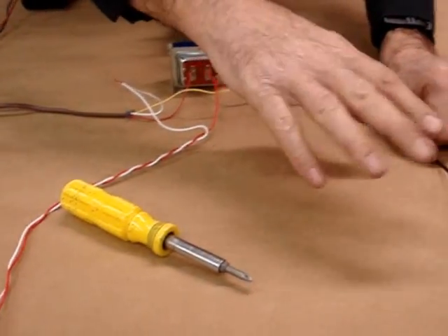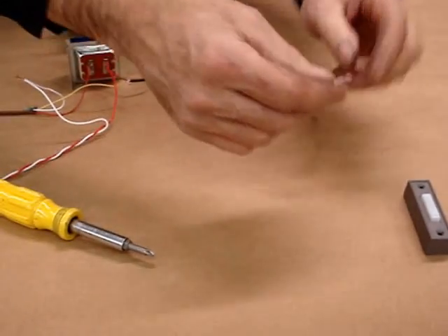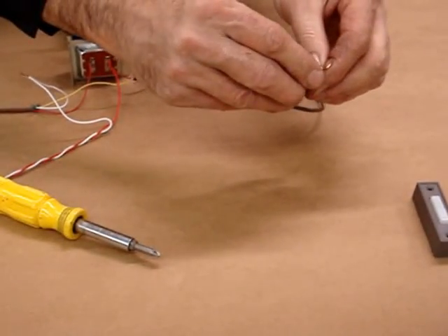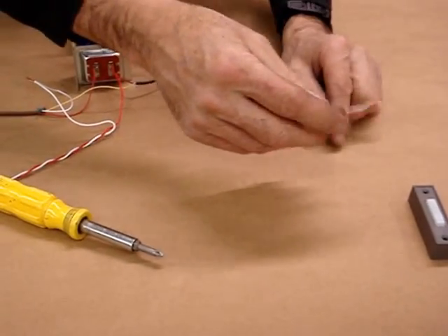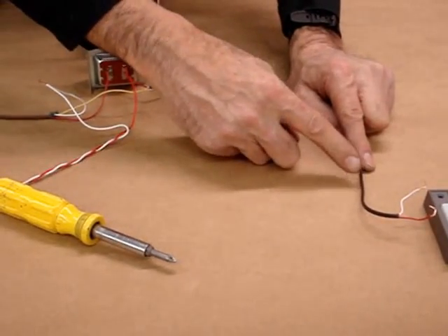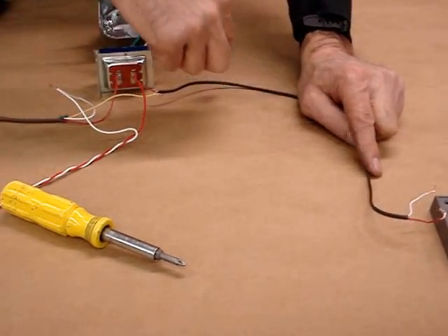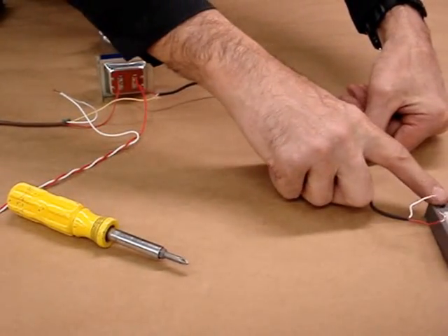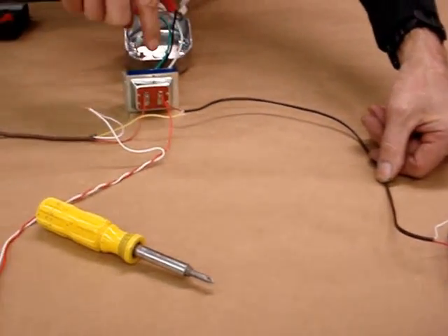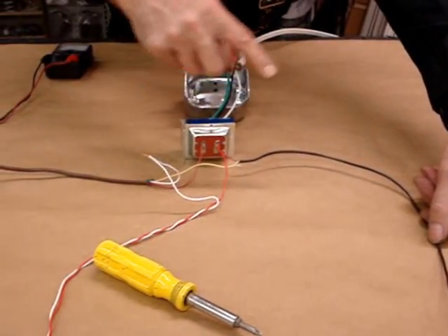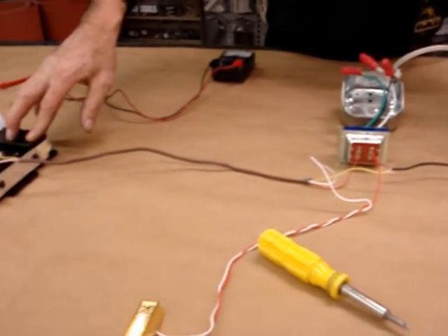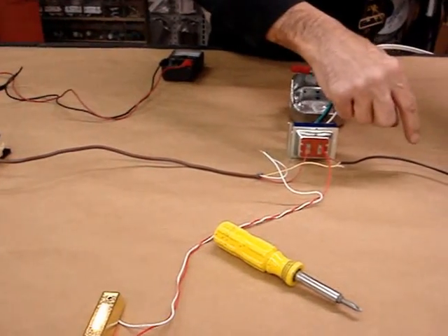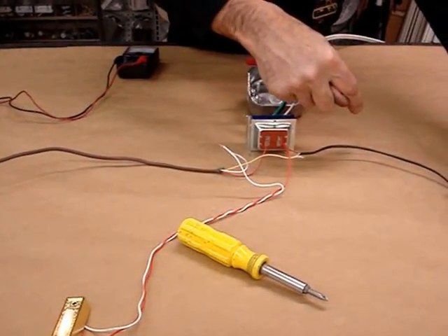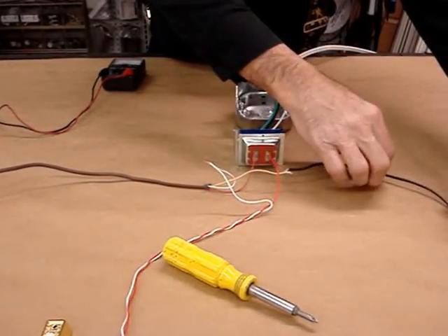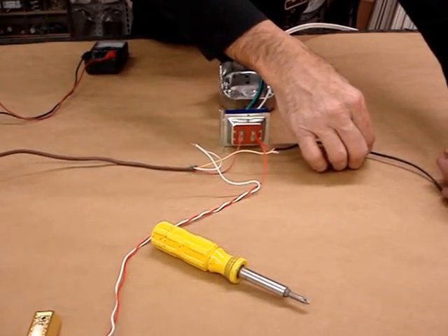Now, when you touch the two wires together and don't get any chiming, a lot of times it's due to a potential short in the line where the wire runs from your front door to the transformer in the middle of the house, then to the doorbell. Occasionally something happens to this wire - a nail goes through it, it's laying on ductwork, whatever - and the wire becomes shorted out.